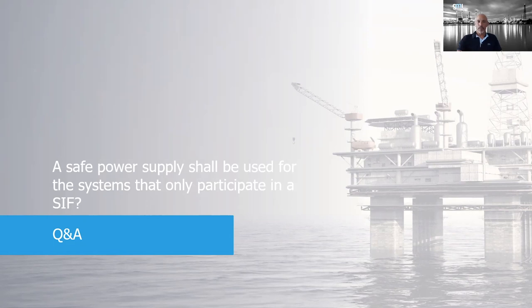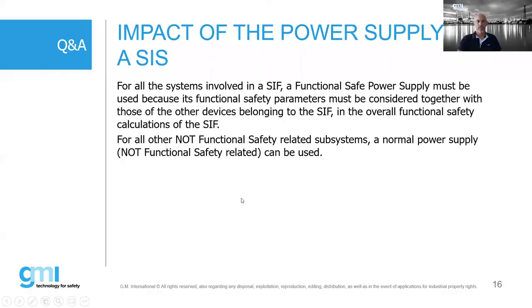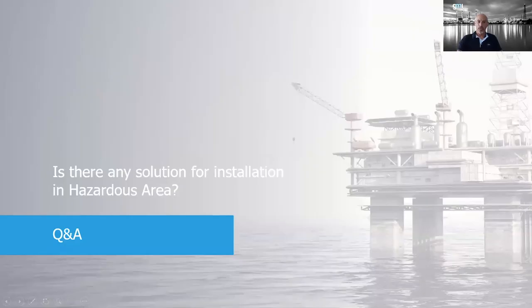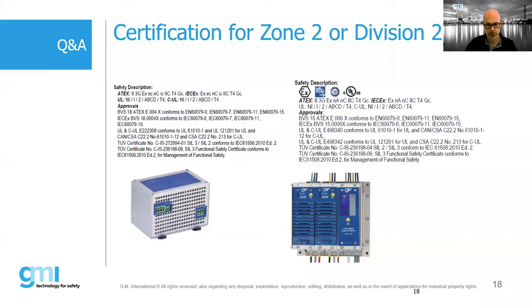Okay, so let's continue with this. A safe power supply shall be used for the system that only participates in the SIF. We already answered this. Okay, is there any solution for installation in hazardous areas? Yes, we do have a solution. Those power supplies are suitable for installation in zone two. Massimo, we can explain a little bit more about this, probably, because there are two slides with the principle of disconnection also. But for the certification for installation in zone two, fundamental is an auto swapping system that the safety power supply has inside, in a rack solution.